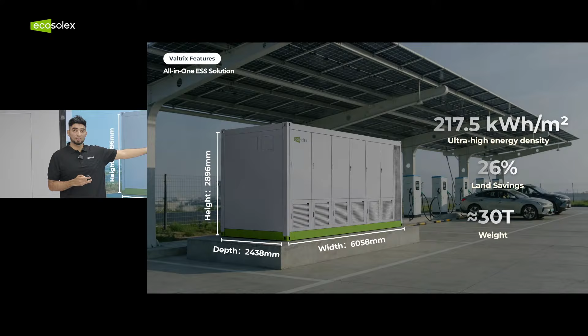Here is the physical specs of our Valtrix, the standard dimension. The height is 2,896 millimeters, depth is 2,438 millimeters, and width is 6,058 millimeters, and the weight is around 30 tons. The key highlight here is the density. We achieve an ultra high energy density of 217.5 kilowatt hour per square meter, and this translates to 26% land saving for your project footprint.